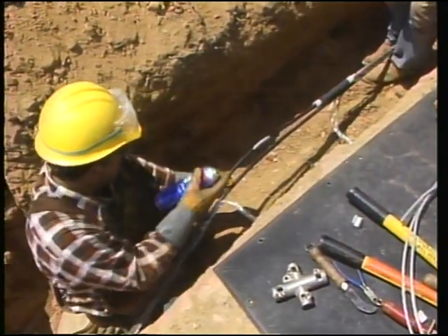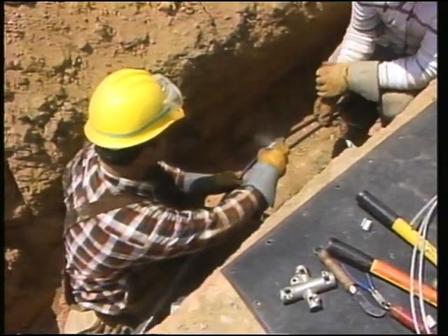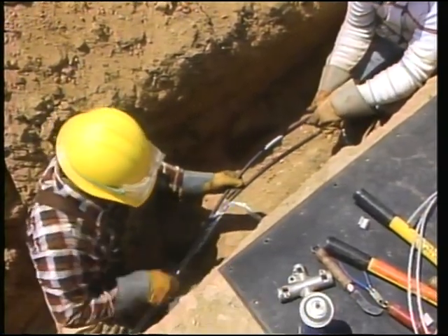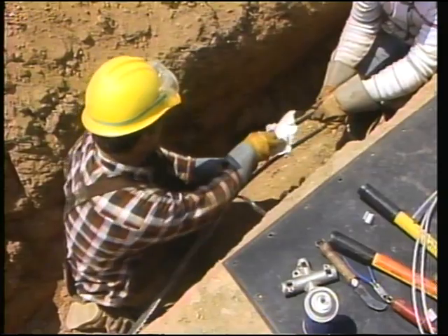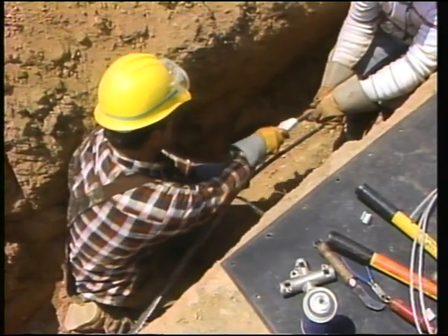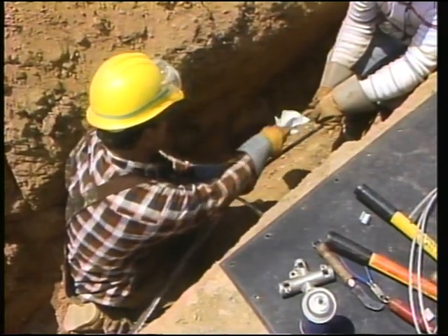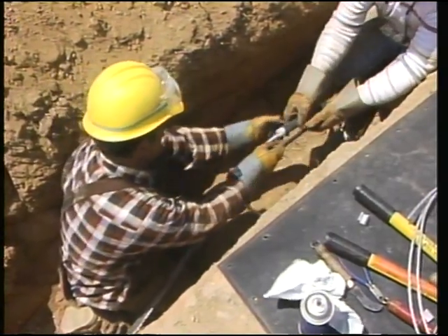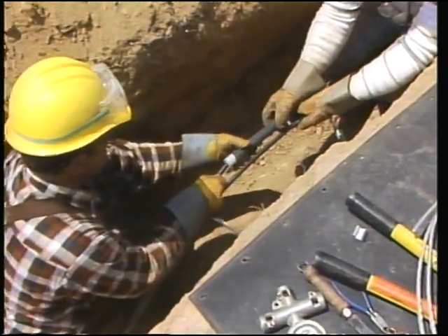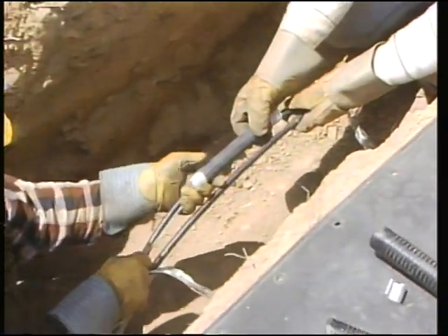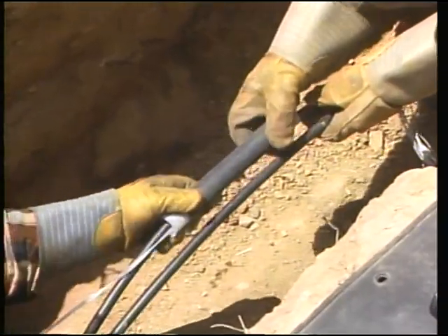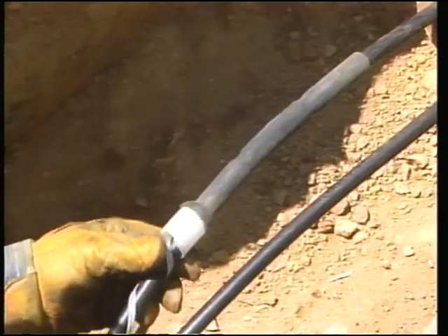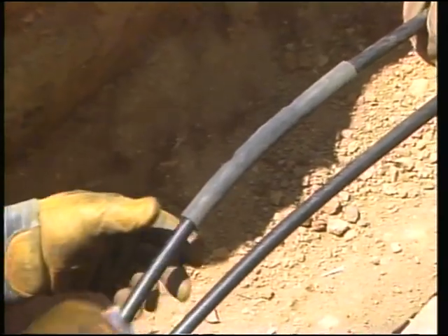A tube that's similar to the heat shrink is the cold shrink. Here, the workman has already placed the cold shrink tube on the cable ends and made the compression splice. The cold shrink splice used here is a rubber tube with a plastic core which has a tab coming out of one end. To apply the tube, it is first centered over the splice. The tab extending from the tube on the other end is then pulled. As this is done, the tube shrinks over the conductor to form a watertight seal.